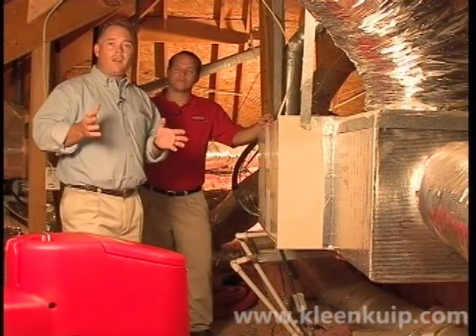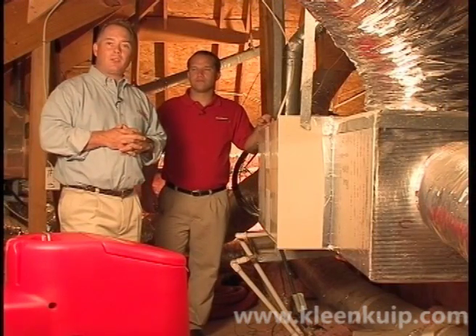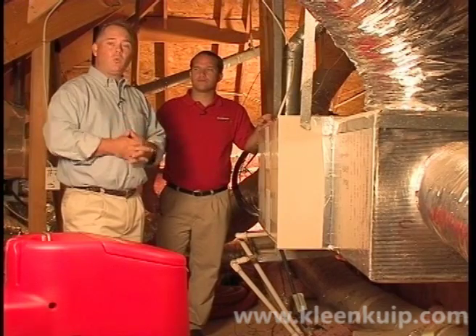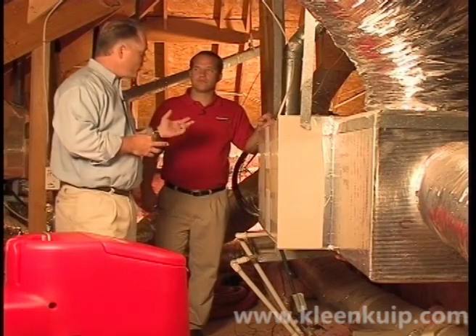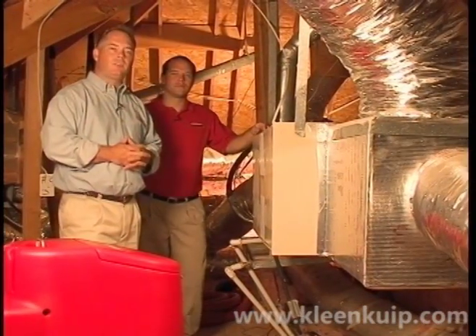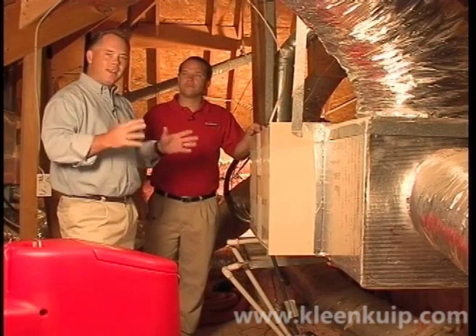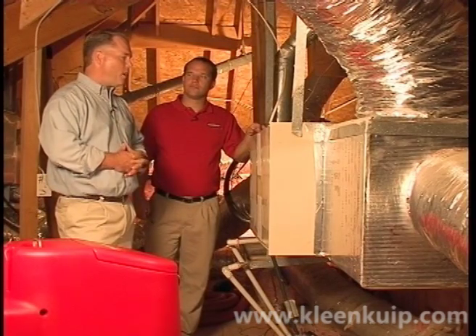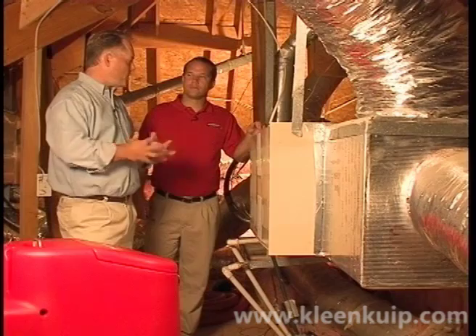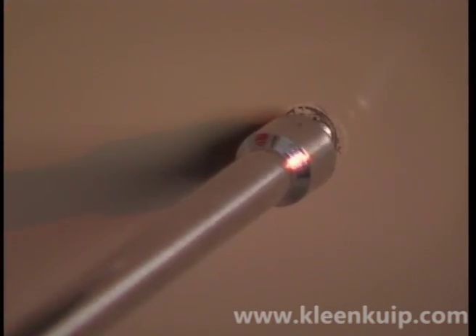Depending upon what your state licensing requirements are, will really dictate how much work you can do within the air handler. The coils themselves are a breeding ground for microbial contaminants, and dander, dust, pollen and mold that accumulate on the coils also decrease the efficiency of the unit. So getting in here and deep source cleaning the system really starts with taking apart the air handler. To do this, you want to start taking off the nuts; here we have a 5/32 nut driver, and taking off the face plates.